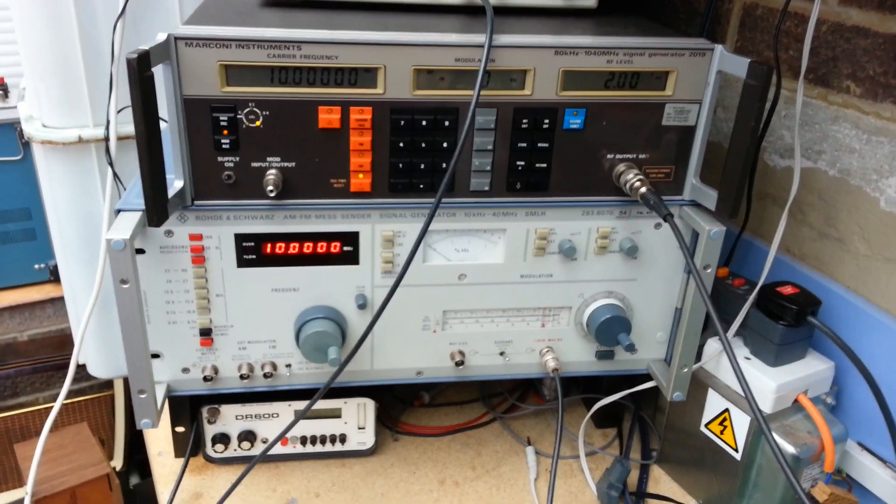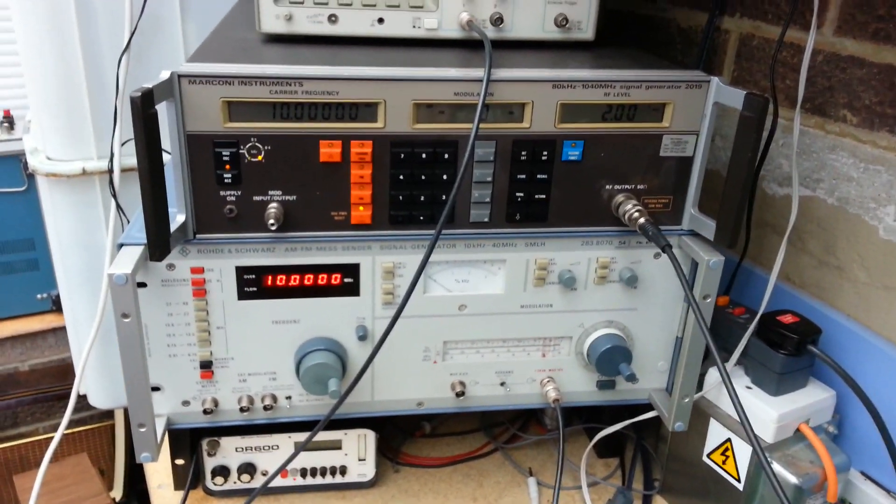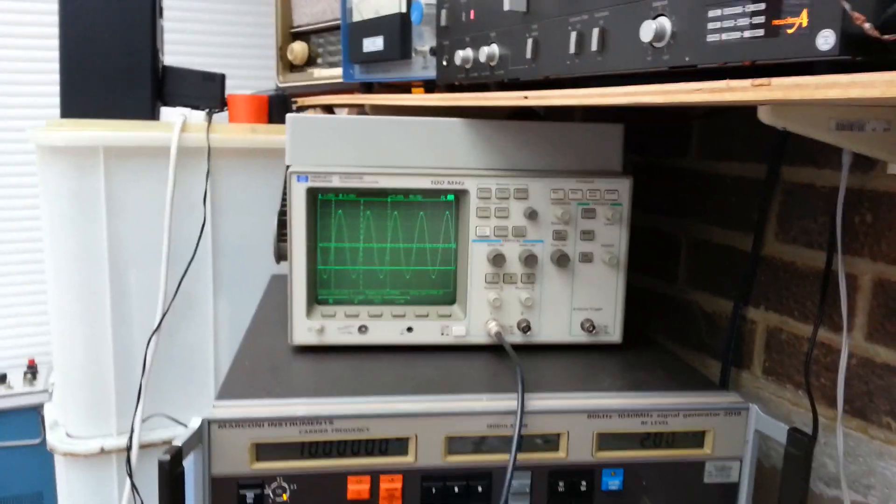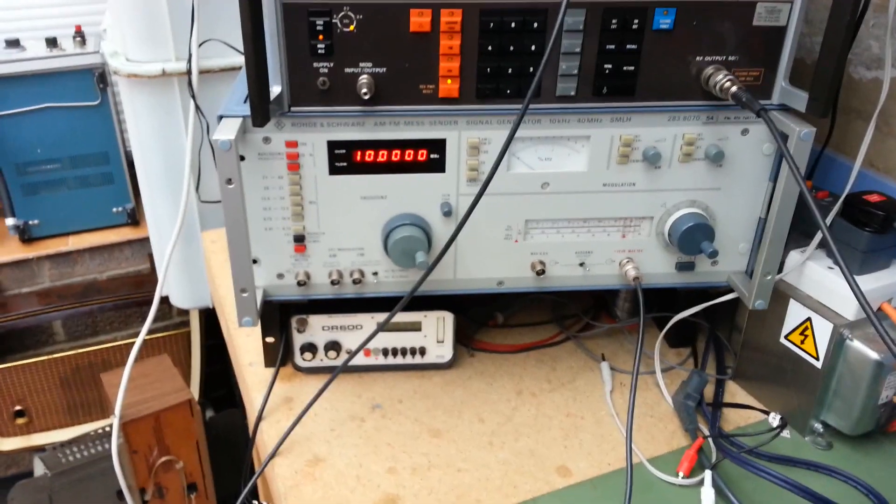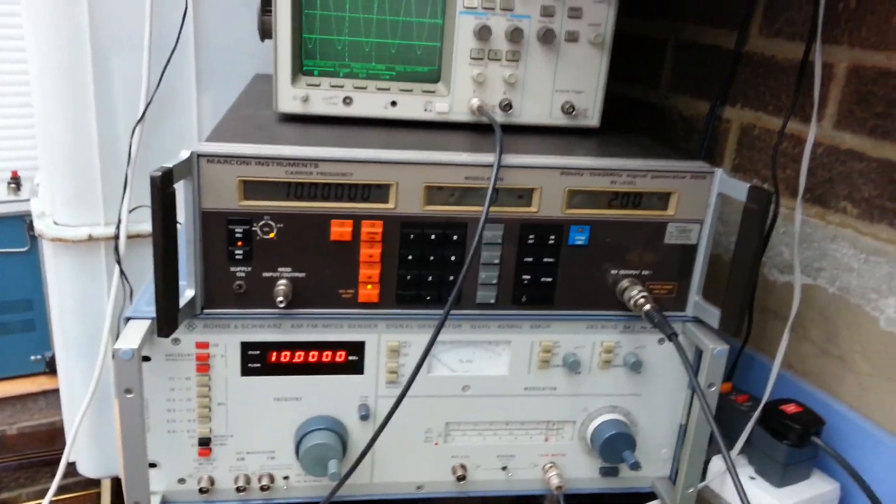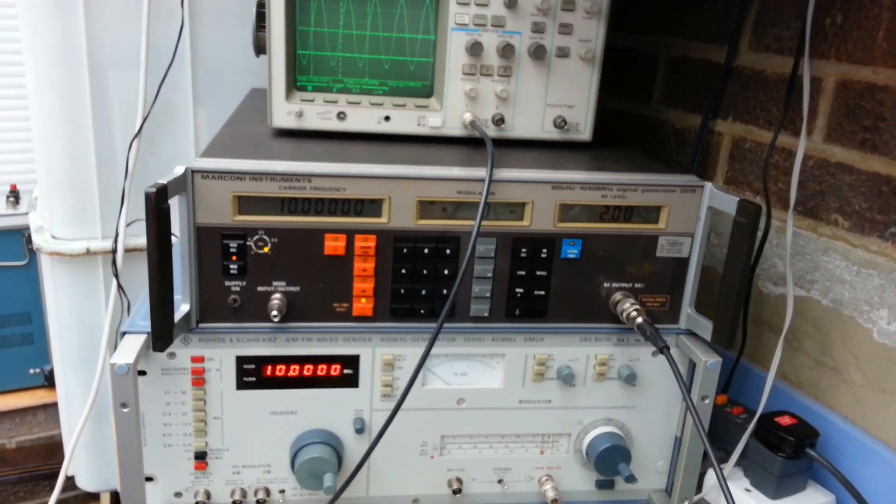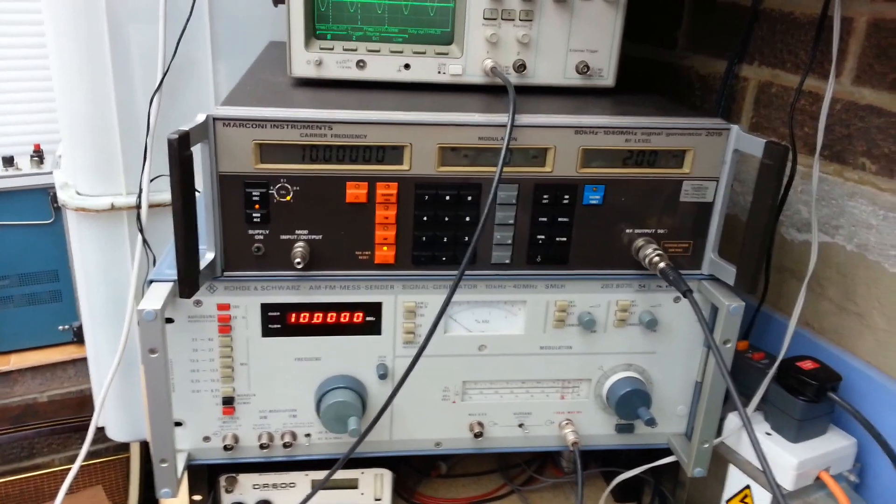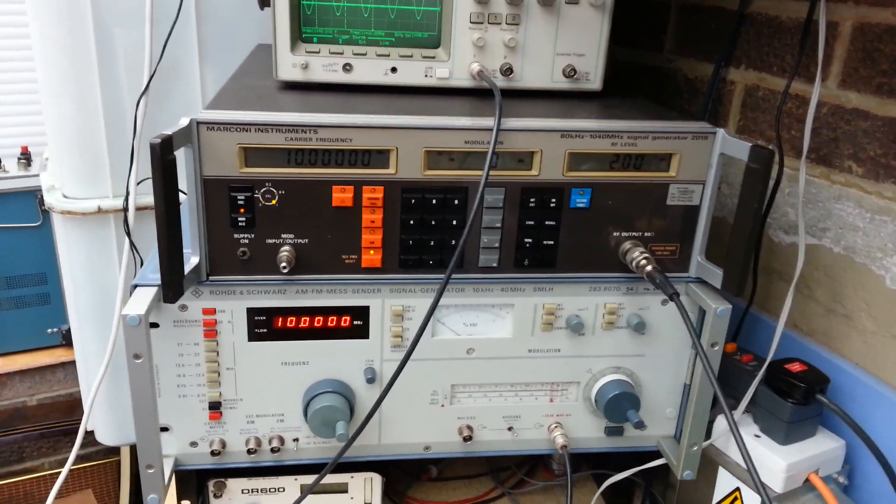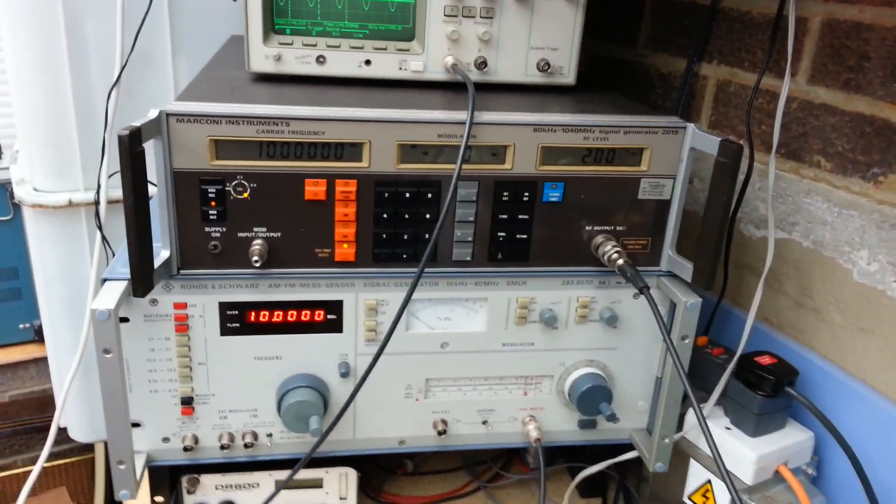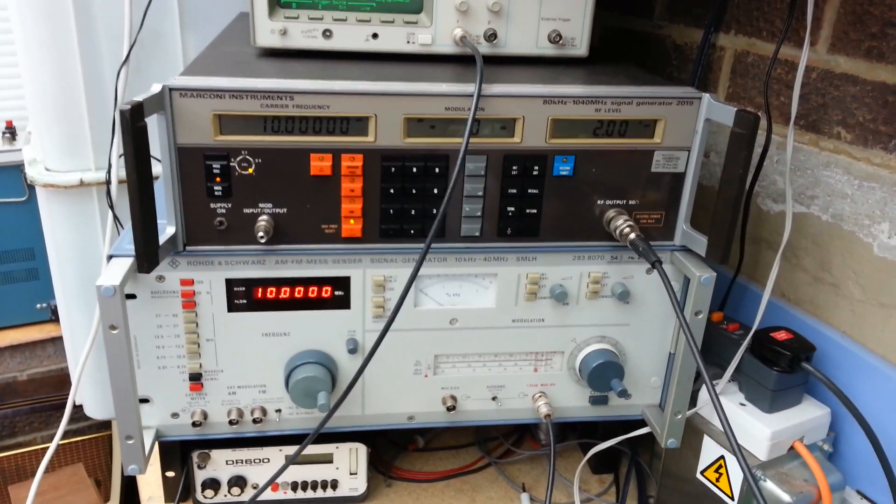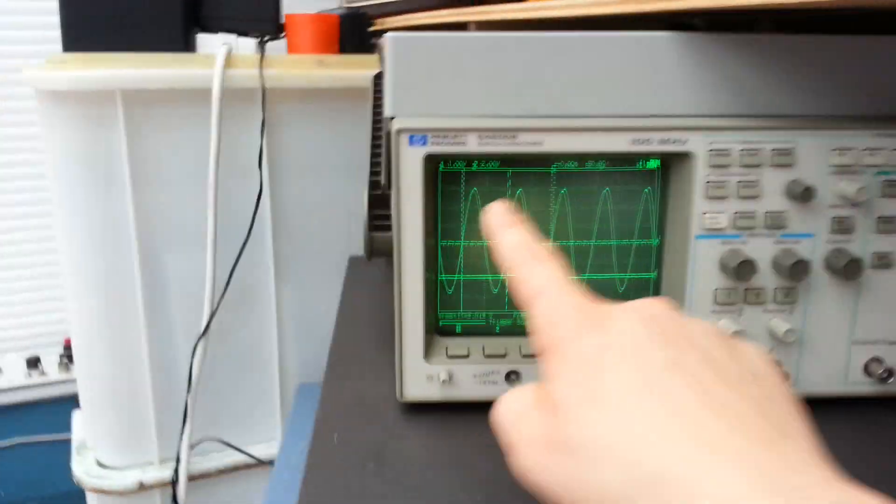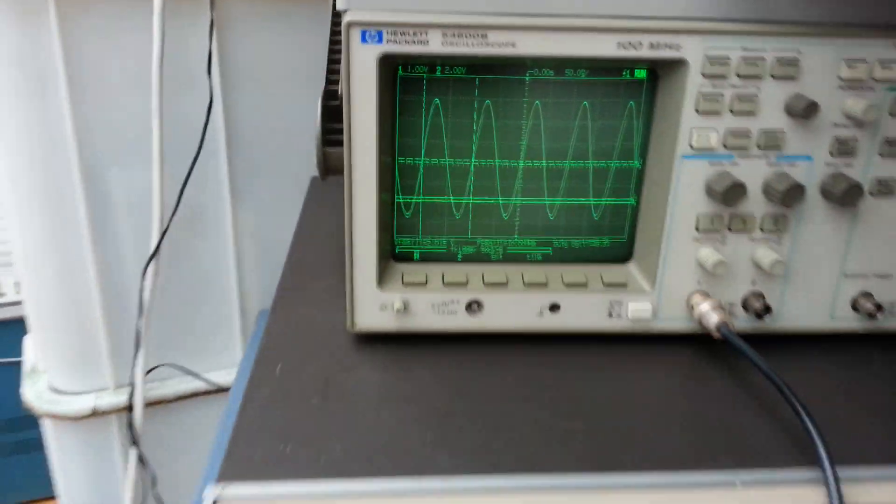It was becoming a little bit temperamental and a little bit glitchy on the waveform output. You used to find that when it was warming up, the output would jump about and become very noisy, almost like it was modulated by some sort of signal going into the unit, which it wasn't. With the modulation turned off, there was a load of noise on top of the waveform.